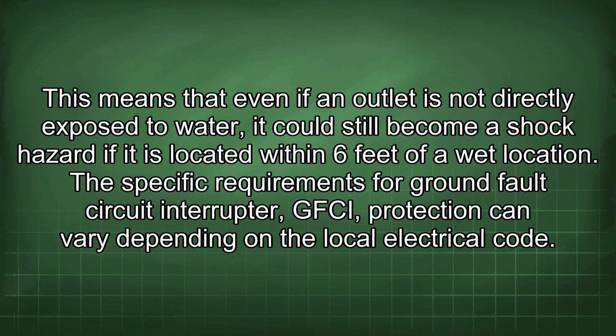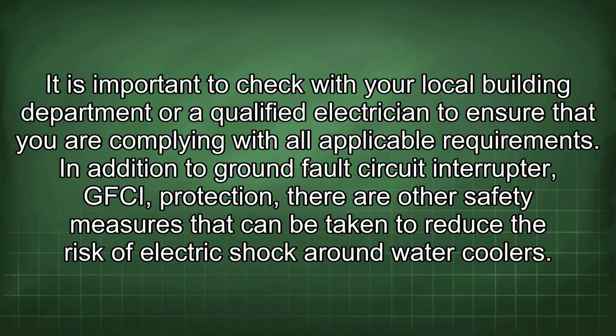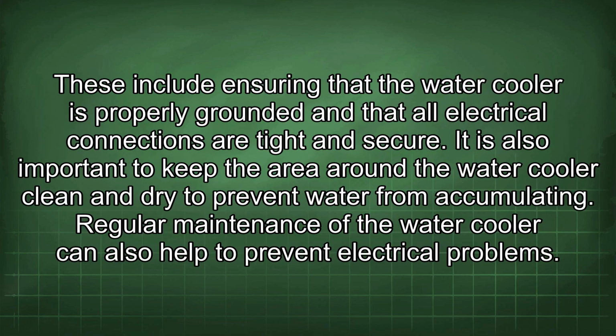The specific requirements for GFCI protection can vary depending on the local electrical code. It is important to check with your local building department or a qualified electrician to ensure that you are complying with all applicable requirements. In addition to GFCI protection, there are other safety measures that can be taken to reduce the risk of electric shock around water coolers. These include ensuring that the water cooler is properly grounded and that all electrical connections are tight and secure. It is also important to keep the area around the water cooler clean and dry to prevent water from accumulating.